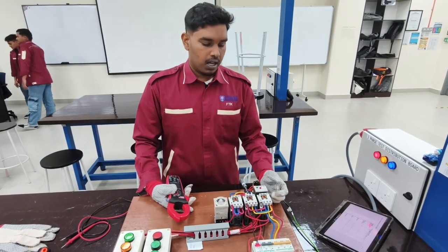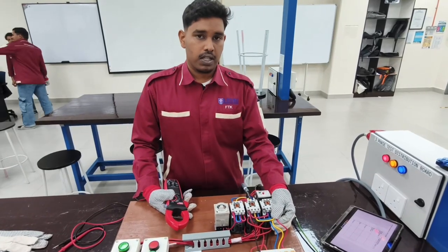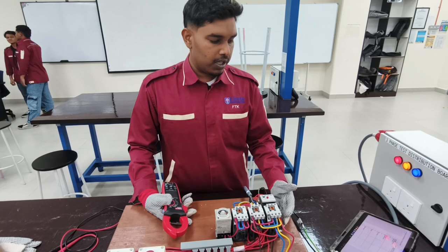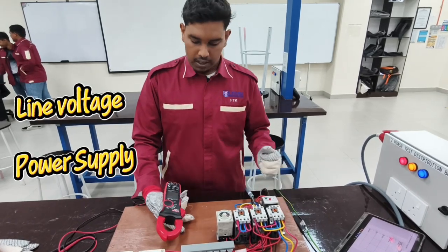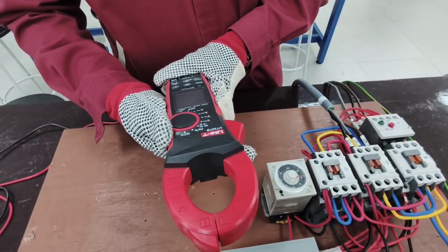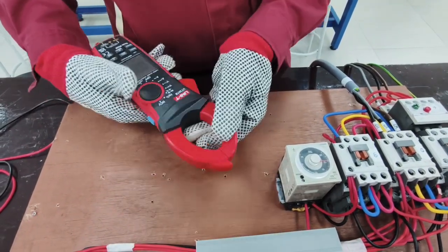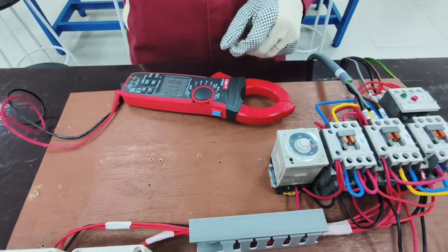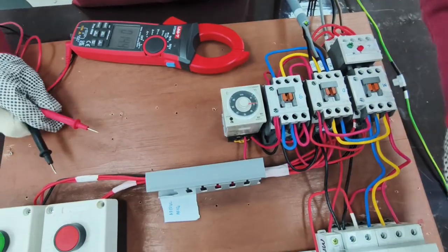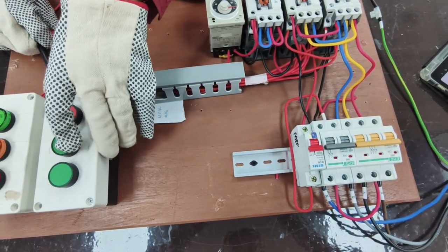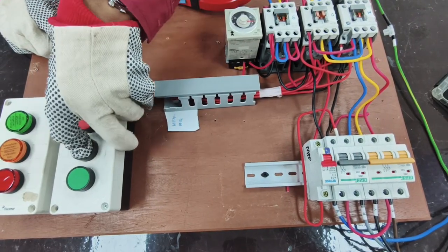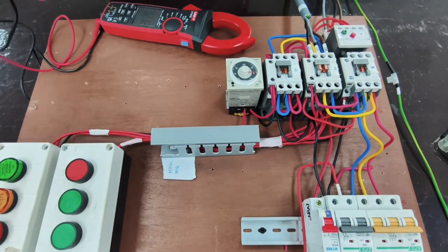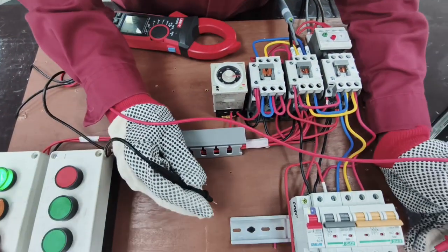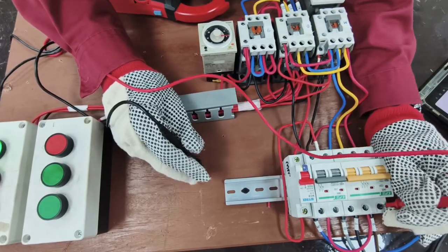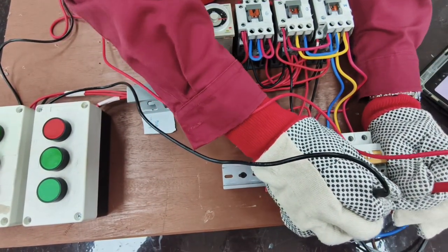Okay, now I want to show how to take reading from our working circuit. The first reading we will be taking is line voltage from the incoming power supply. To take the reading of voltage, we need to set to the voltage AC, because we are using AC current, and then this is the incoming power supply. So we will turn on the circuit and take the reading. We have 2 probes, 1 probe on the red and 1 probe on the white. This is line voltage. We can get 417 volt.